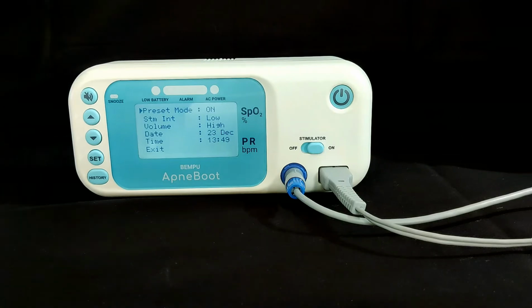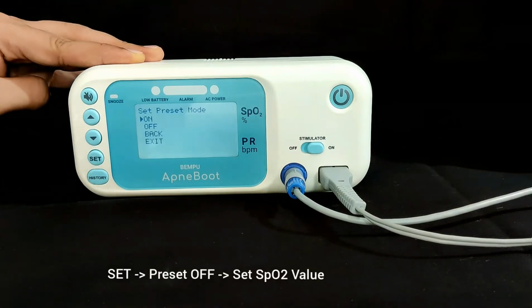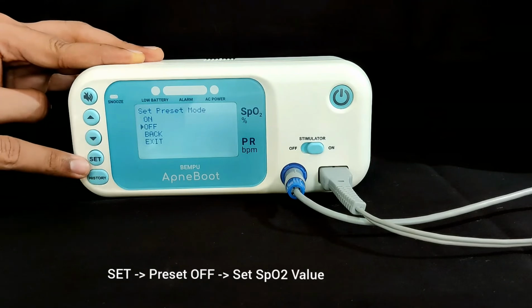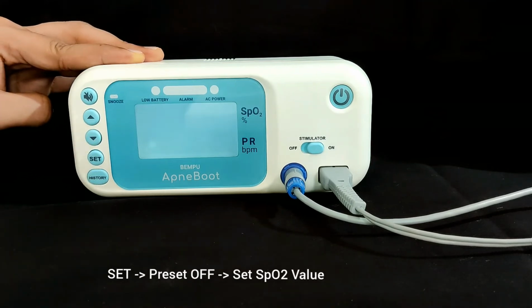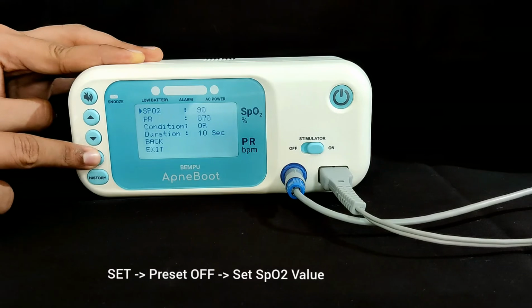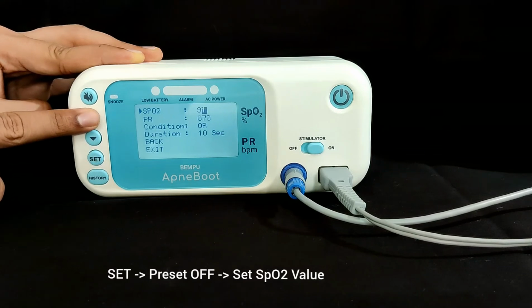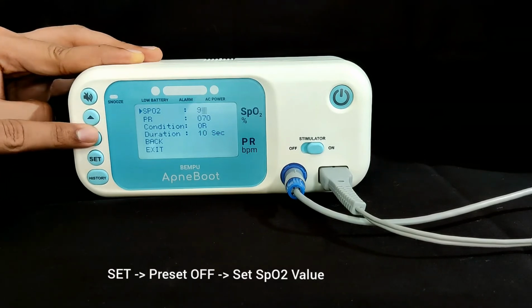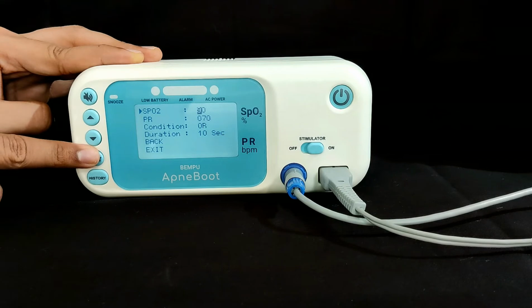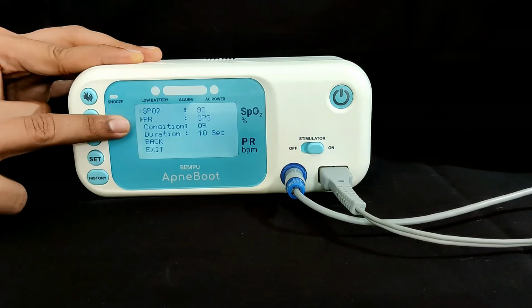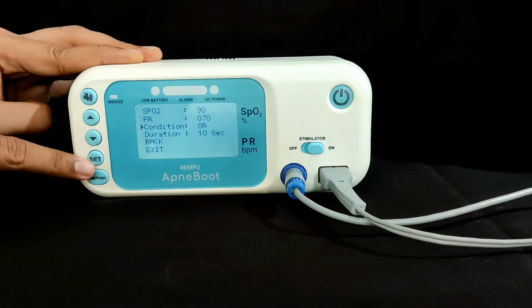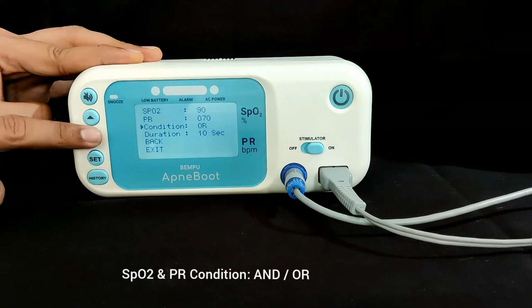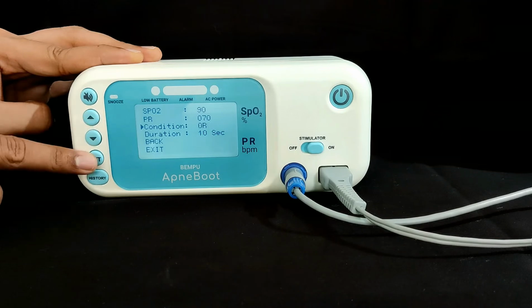To do so, press the Set button. Change the preset mode to Off by pressing the Set button again. Then select SpO2 and set the numeric value using the arrow up and down buttons. Repeat the same to set pulse rate. Next, you can also set the relationship between the SpO2 and pulse rate as AND or OR condition.